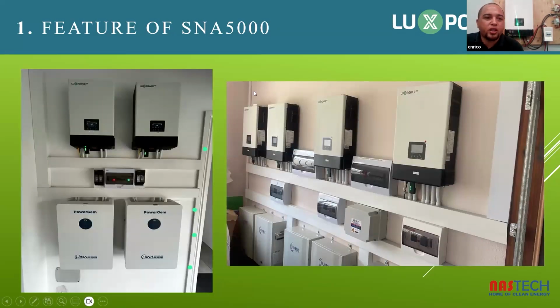Here's an example of two installations. This is a parallel installation of two SNA 5 kilowatt inverters with two PowerGems. So as you can see from first inspection, each inverter has its own battery disconnector, meaning that each battery is connected to its own inverter. I can't necessarily see that these two are in parallel, but you can have them split onto sectioning your house. So you can section your house with one inverter providing power, 5 kilowatts, to one section, and then on another section, the other 5 kilowatts.